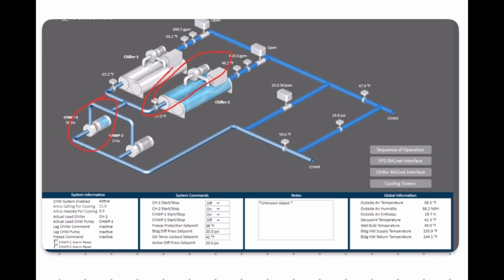Your water is gonna be running. You're gonna have a return and a supply. Again, a return and a supply. Supply is what you give to the building. Return is what you get back from the building or from the air handlers. So from the air handlers or the building, you're gonna have a chill water return that is going to run through the left side on these lines over here. Your return goes through there, and that's coming from the air handler units. Your return comes from the air handler units, or if you want to call it from your building, then goes through this pump in this case, and then to your evaporator.